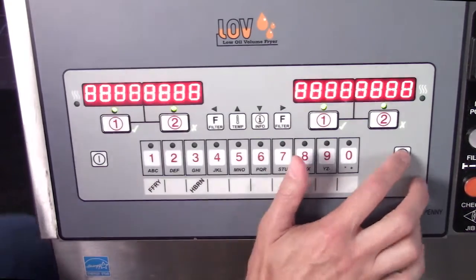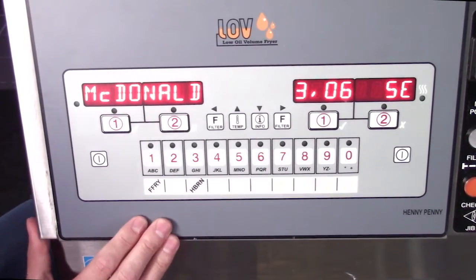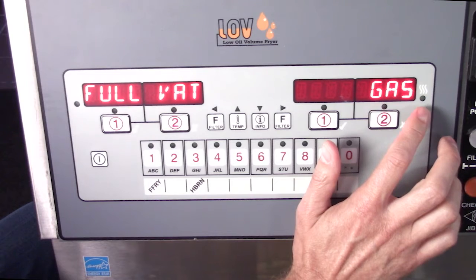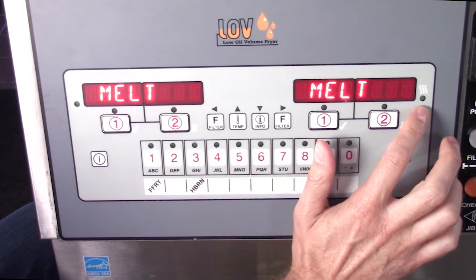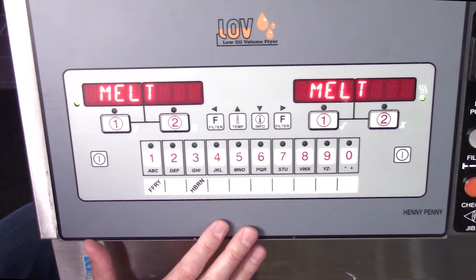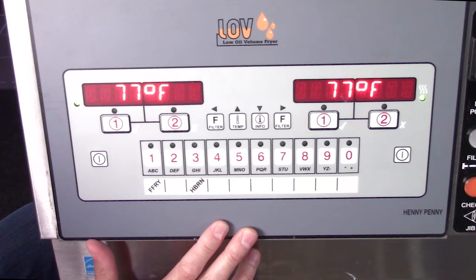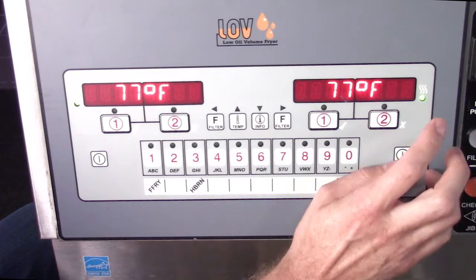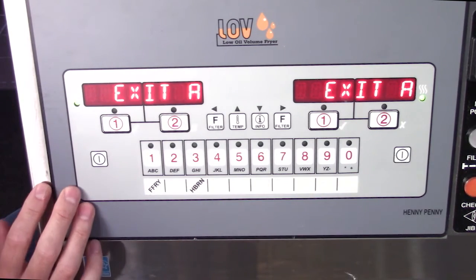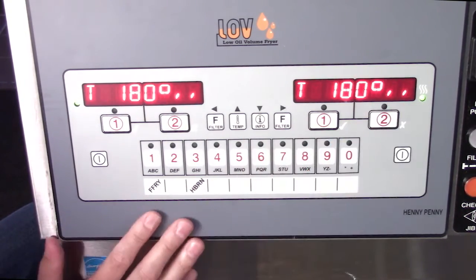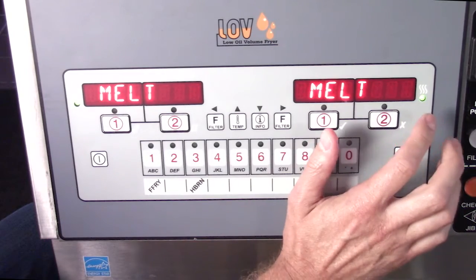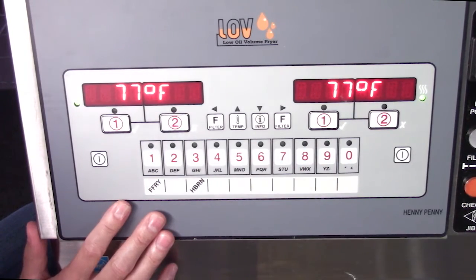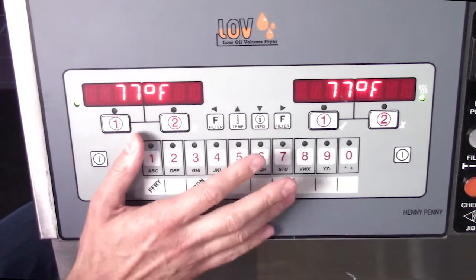So let's turn it on. Slowly, blinking rapidly. We're sparking. Now it's solid. So now it means that I have my flame sense, my pilot's lit, so now it should be calling for heat.